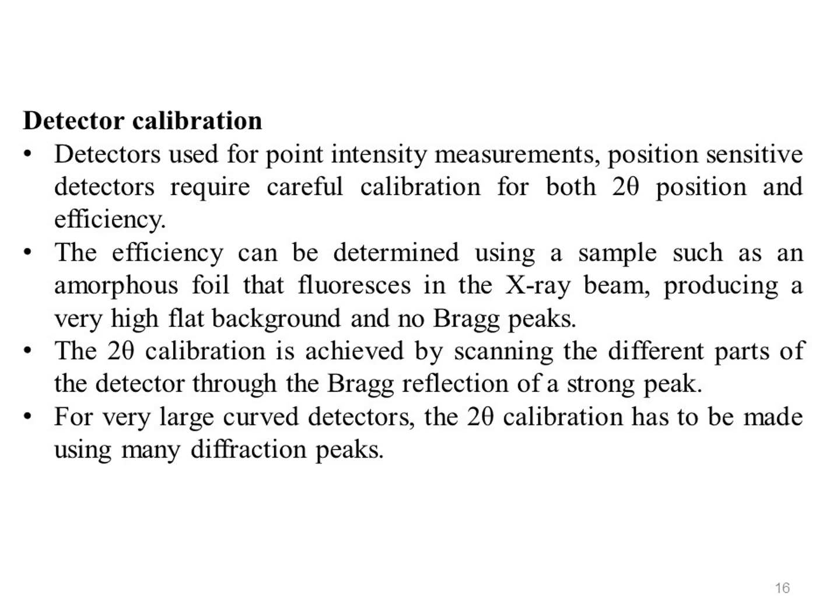Sealed gas filled PSDs should be recalibrated whenever the gas is replenished, in contrast to detectors with a continuous flow of gas that need checking regularly.